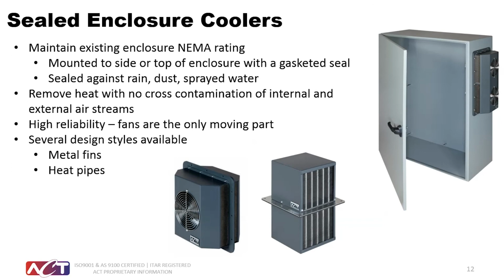Sealed enclosure coolers are popular for above ambient cooling because they allow the designer to maintain the NEMA rating of the existing cabinet. As mentioned, the design of the heat exchanger prevents cross-contamination of the air streams, which allows heat to leave the cabinet without letting any dirt or water back in. Sealed enclosure coolers are viewed as highly reliable because the fans are the only moving component. Metal fins and heat pipes are the two commonly used heat exchange mechanisms found at the core of most sealed enclosure cooling products.